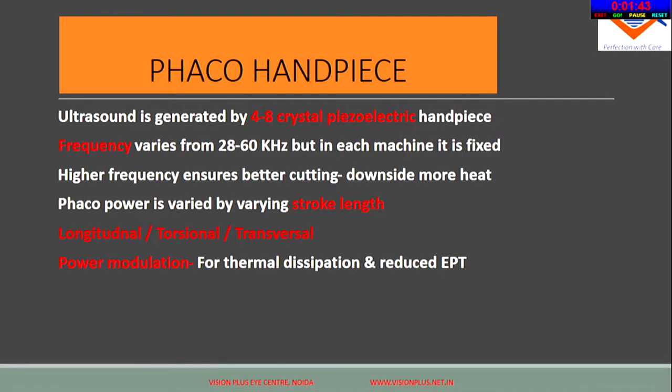Coming to the handpiece, which is the heart of the machine: PHACO is basically a reverse piezoelectric phenomenon. The frequency is machine-based and can vary from 28 to 60 kHz. Lower frequency means less heat generation; higher frequency means better cutting power but more heat generated. PHACO power can be varied depending on stroke length. Earlier only longitudinal ultrasound was used, but now later machines have torsional and transversal ultrasound, which helps reduce effective phaco time. Different power modulations are available in different machines, giving clearer corneas the next day.